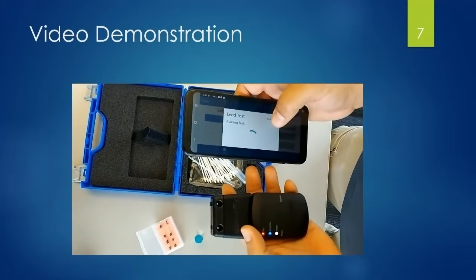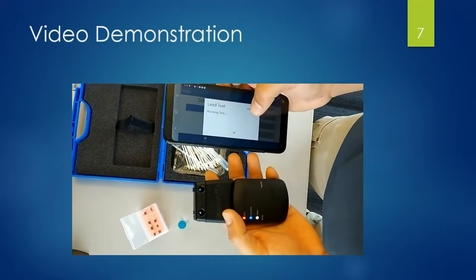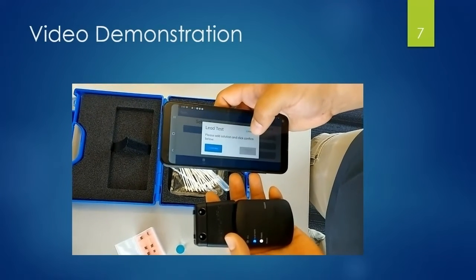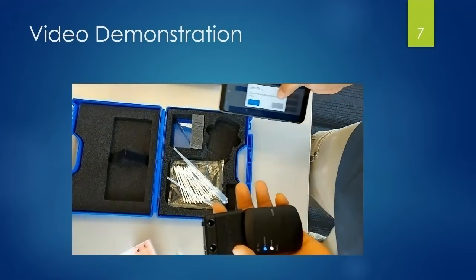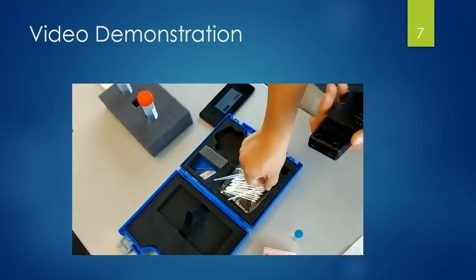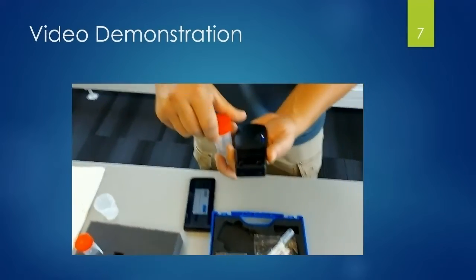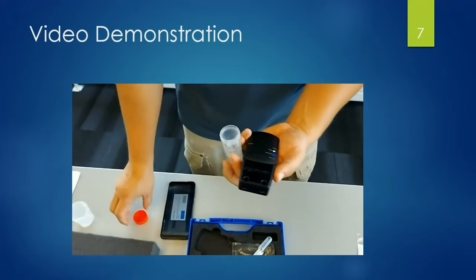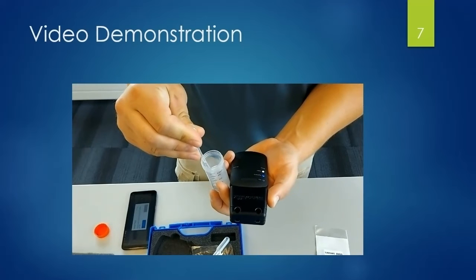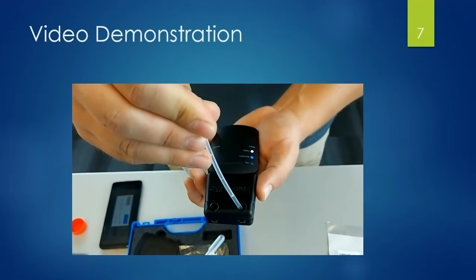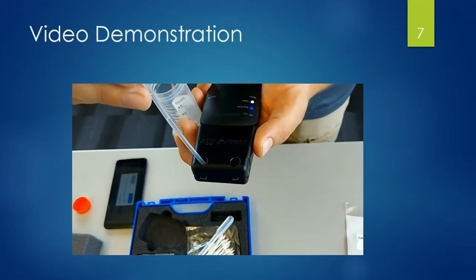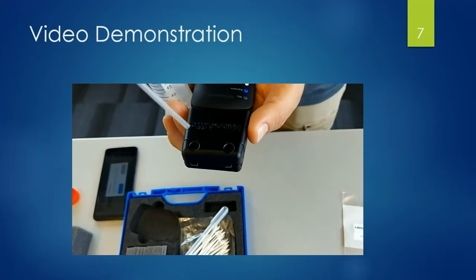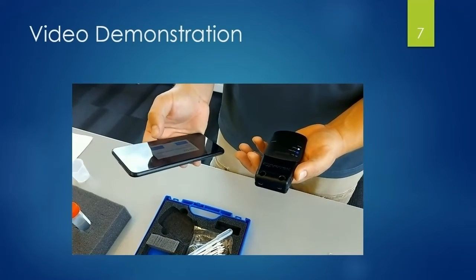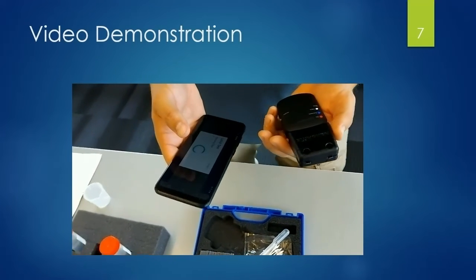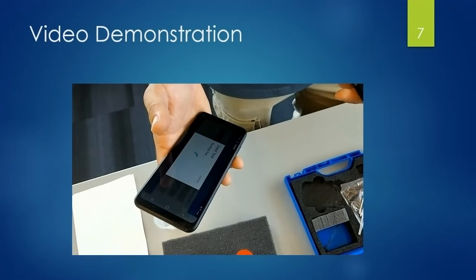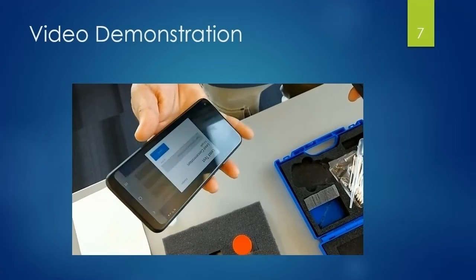Hit Start and it'll run a background scan on the dry sensors. Once this test is completed, add your water sample to each of the two devices, 200 microliters to each sensor. Confirm and hit Start. The entire test takes about 30 seconds. And in the end, you'll get a reading of your lead in parts per billion.